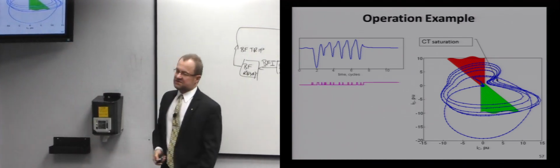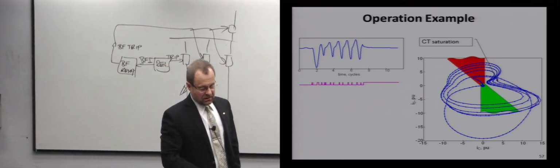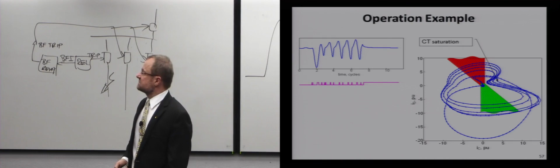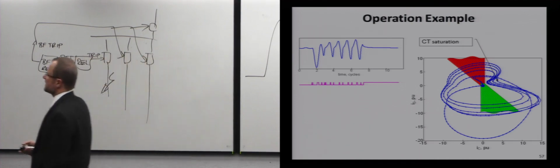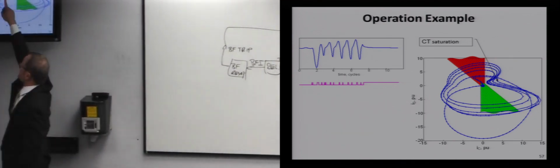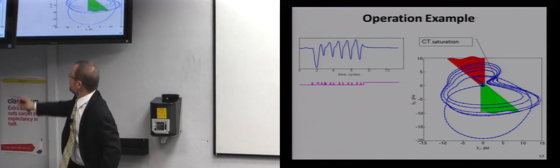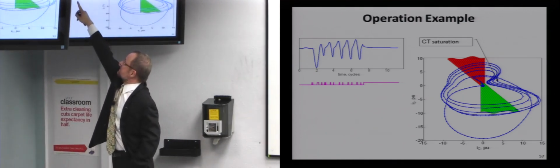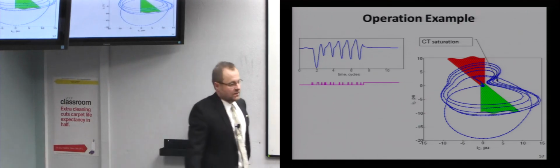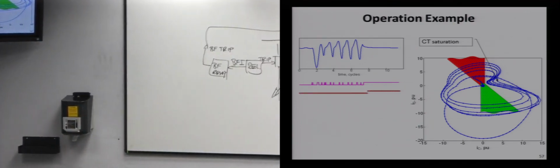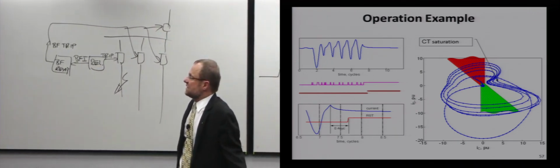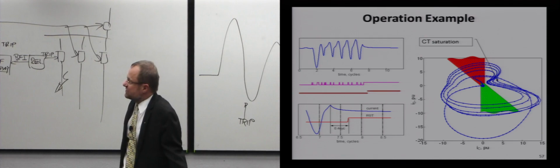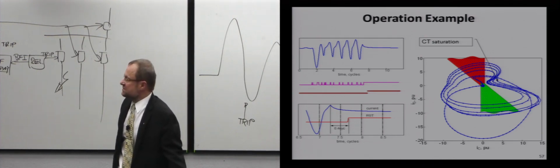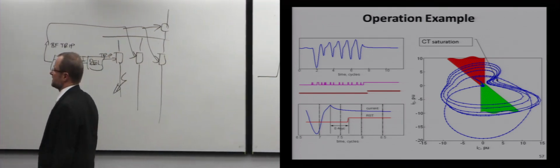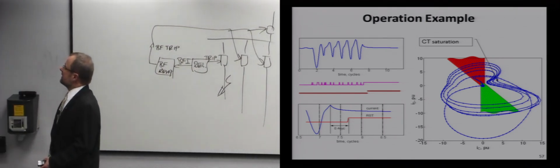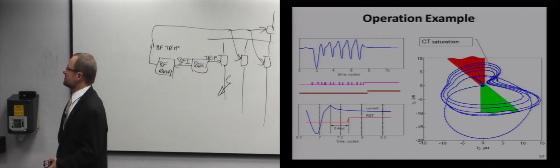So this flag is basically telling me, you are inside one of these cones. So I'm in and out, and when the current is interrupted here, I stay. Oh, excuse me. I stay, and I never leave that cone. So I have a permanent assertion. My timer expires shortly after that, and this is when I declare that the current is gone. So in this case, my reset time is 0.4 of a cycle, compared with a cycle and a half for a brute force other solution. So again, this is very good performance.